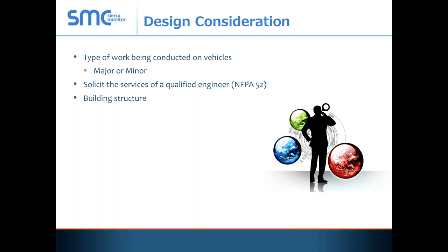We also consider the building structure itself. There's a building that Mark has with a sawtooth roof design, and that became quite a potential problem in design. We had a sawtooth building that, as far as having detection and everything else, just did not work out. It would have been so expensive, and the building was probably built in the 1920s — we had no way to attach ducting to it, no structural plan. So we ended up building them a 230 by 40 foot canopy so they could take some of these vehicles outside to repair. We put in all reels, electric, and everything else, but there was just no way to convert that building. Those are things you have to look at with your structural engineer on the design.